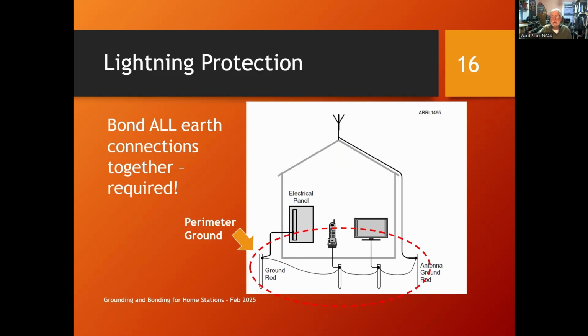What happens if you have 1,000 amps from a lightning surge? It doesn't even have to hit your house. It'll just flow through the earth as the charge rebalances. What happens if you have 1,000 amps flowing for a short period of time through the earth between two ground rods that have 10 ohms of resistance between them? Well, 1,000 times 10 is 10,000 volts. And suddenly you've got 10,000 volts between your phone ground system and your home entertainment system ground system.